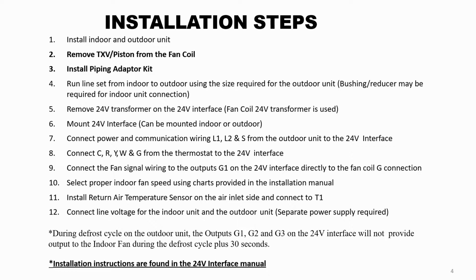Once you've removed the expansion valve, the third step is to install the piping adapter kit that's going to connect where the TXV used to be connected. If you have a unit that has a copper coil, the piping adapter kit is not required, as you'll simply cut and braze the connection at the indoor unit. The next step is to run the line set from indoor to outdoor using the size required for the outdoor unit. A bushing or reducer may be required for the indoor unit connection depending on the combination of units that you have.